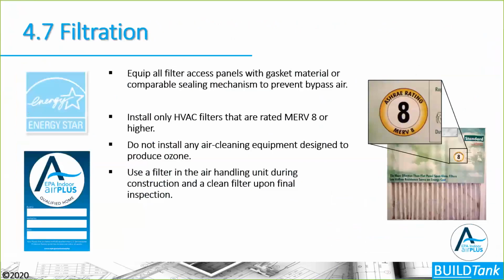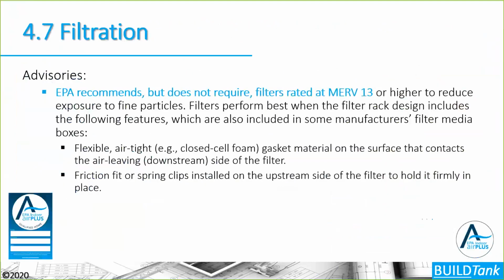Filtration systems. We talked about having filter access points that are gasketed and airtight that ensure that the air is moving through the filter and not bypassing the filter. The EPA recommends higher MERV filters, but they don't require that. You only have to use MERV 8 as a minimum requirement. And then there are some requirements for that filter access: being airtight, ensuring that it's gasketed and that the air is flowing through the filter.